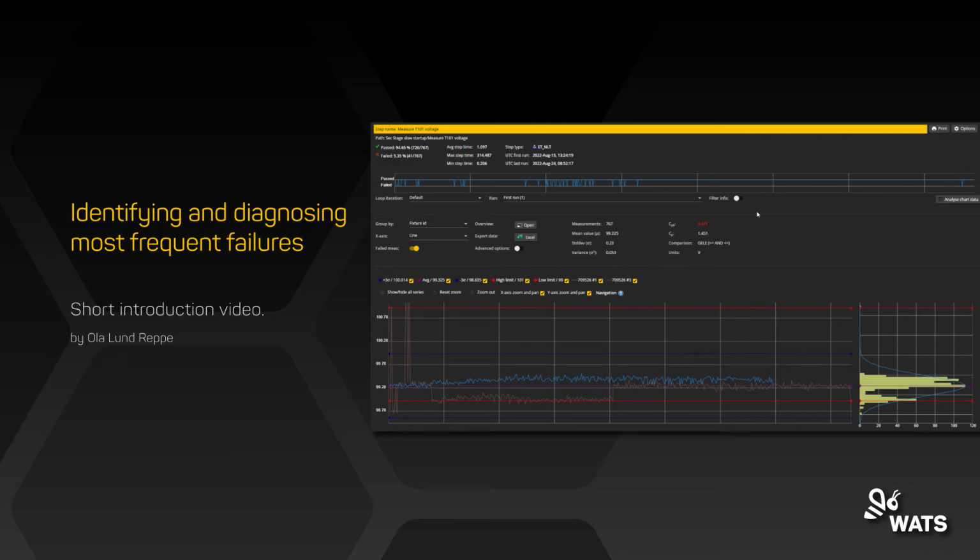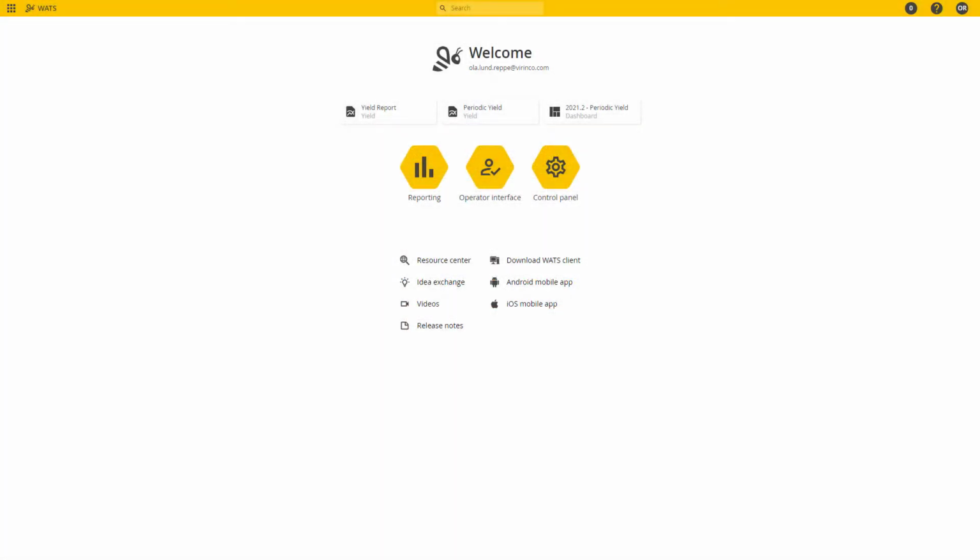One of the key benefits of using WATS is the ability to quickly identify underperforming test operations and your most frequent failures. In this video, I will demonstrate how to identify the worst performer among my top runners, then identify the steps that cause the most failures and try to diagnose the most failing issue.